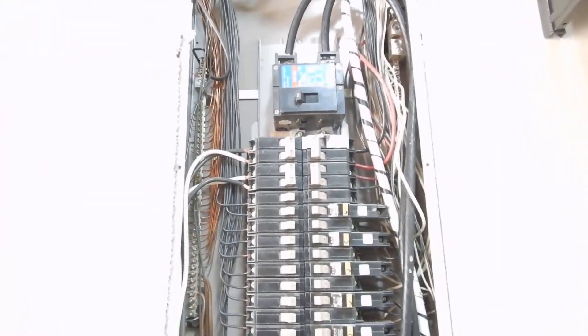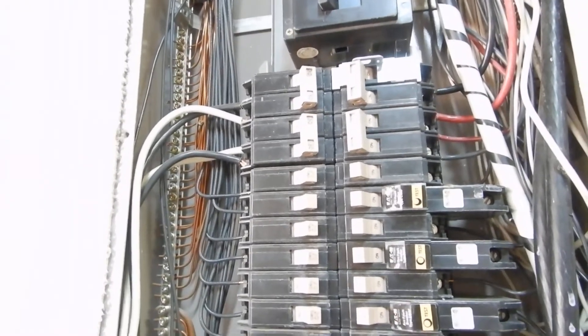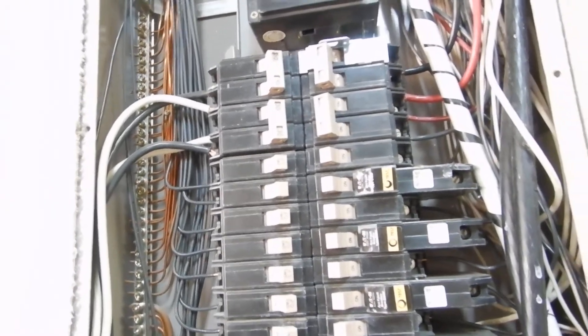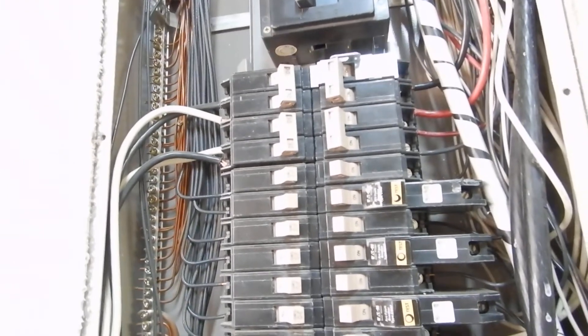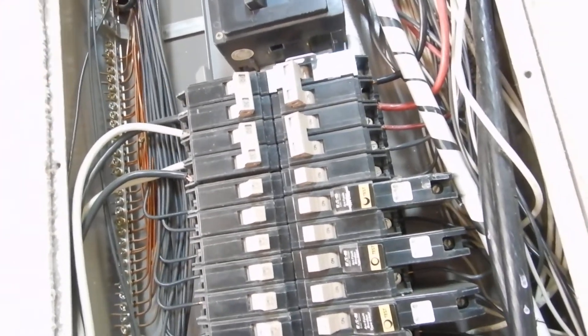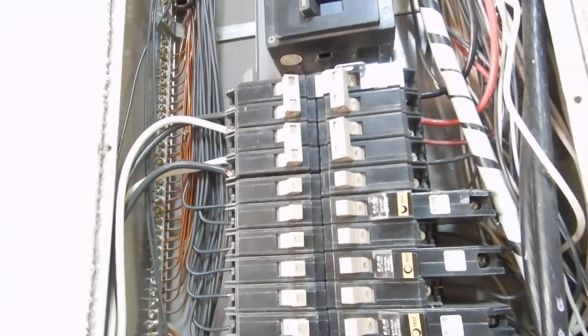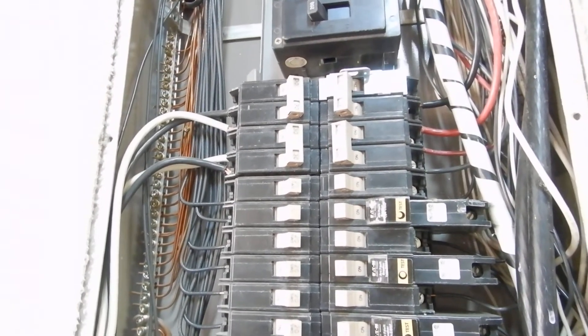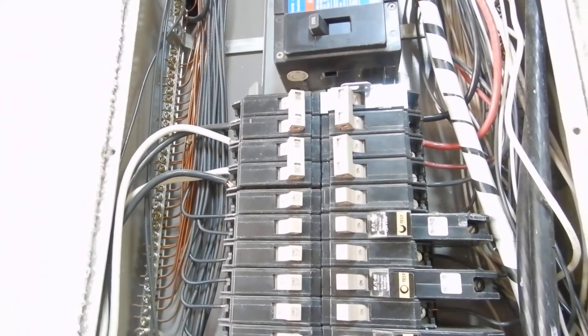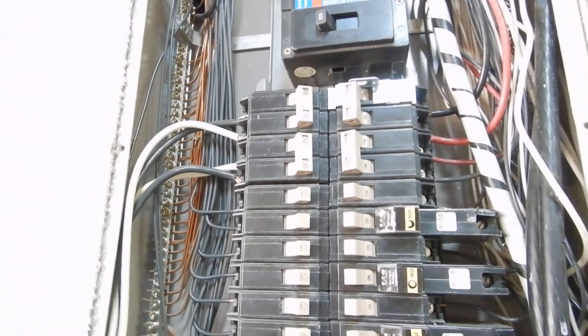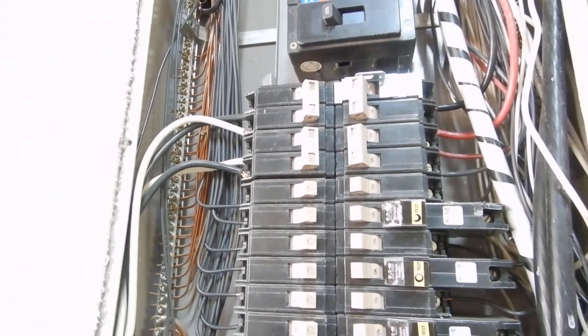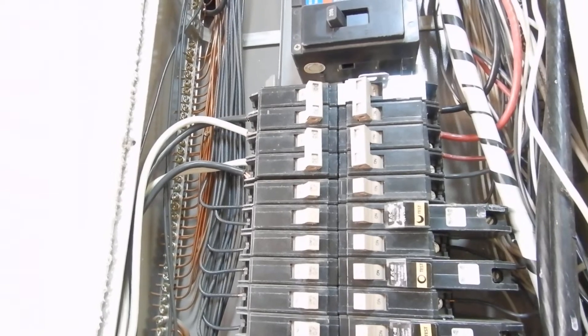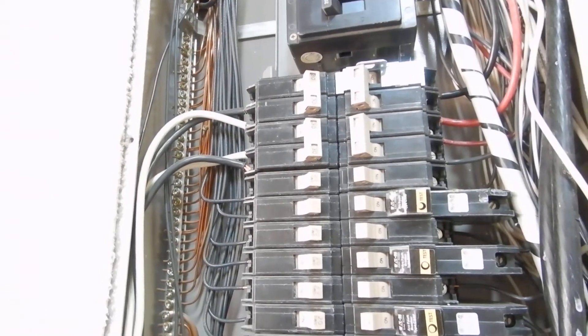The manufacturer wants to see the largest size breakers. So, well, the units are 15 to 16 years old. They're about to be replaced. Do you think the new units are going to use the same size breakers? I don't. I think you're going to be a lot more efficient. I think these breakers, some of them might even be oversized. So just replacing the breaker on a 15, 16 year old air conditioning system, I don't know if that's your wisest move. It might be an unnecessary exercise.